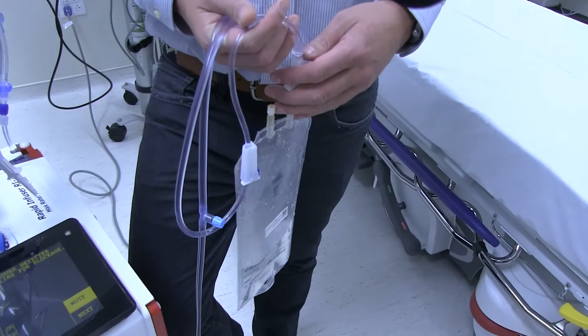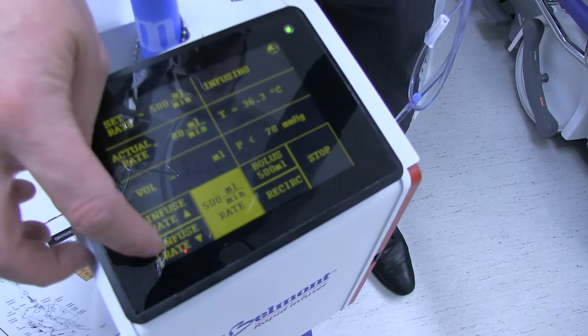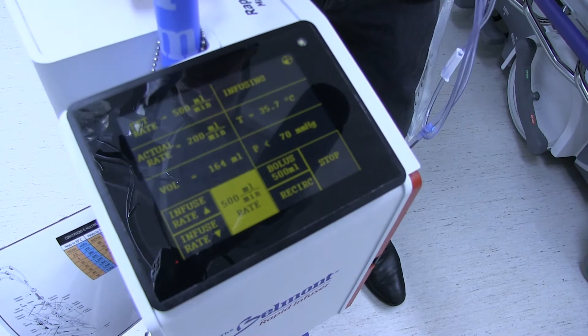So right away, if you look and do not see an occlusion on the patient line, you've got to figure that it's the catheter that's causing the pressure. So you say, okay, you press next, and then decrease the rate before the rate speeds up and causes the same pressure with the catheter.